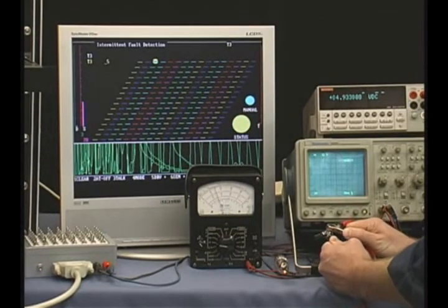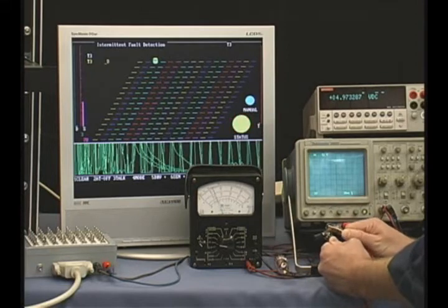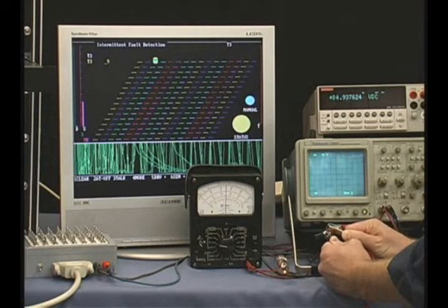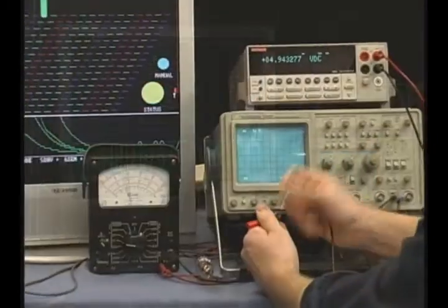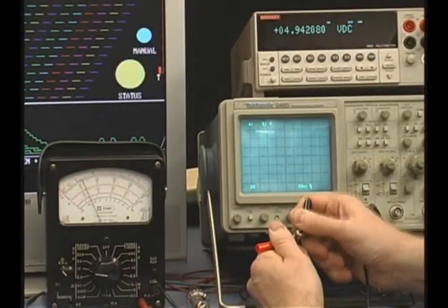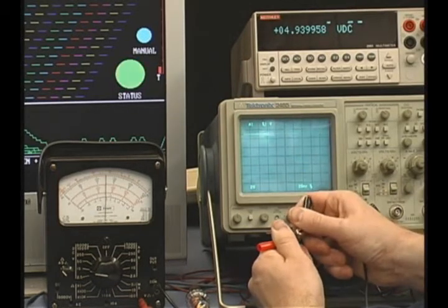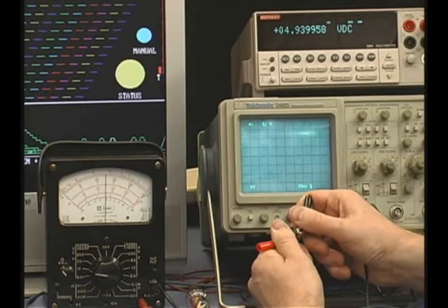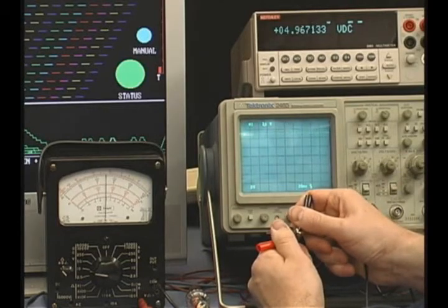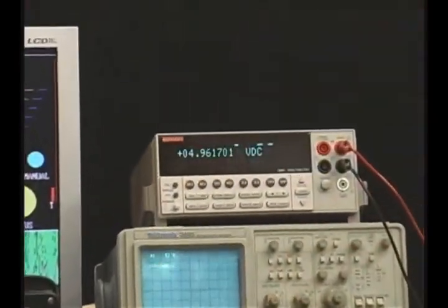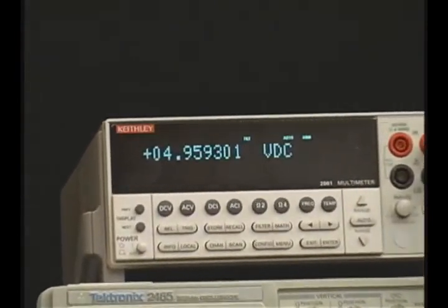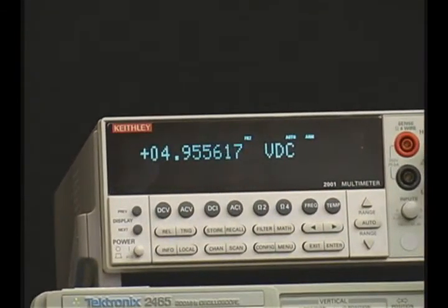As we speed up the intermittency that we are creating, you are going to see some of these devices start to drop out of being able to detect any intermittency at all. The programmable digital multimeter is the backbone of the testing industry. As you can see, the meter has a difficult time tracking the voltage changes that I am creating. This difficulty is due to the high levels of digital averaging that are employed in the meter to enable it to reach its high levels of accuracy.